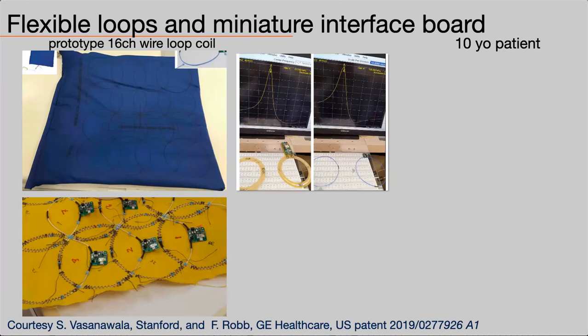These coils, in addition to the interface electronics, are also able to provide excellent isolation between the elements, as seen in the video. What I'm going to show you is you look at the resonance of one coil as you move another coil next to it, and you can see how the traditional one basically gets destroyed in terms of resonance, but the one on the right is pretty much untouched. There is a little bit of interaction, but much, much less than the traditional coil, because of the amount of current on these loops.